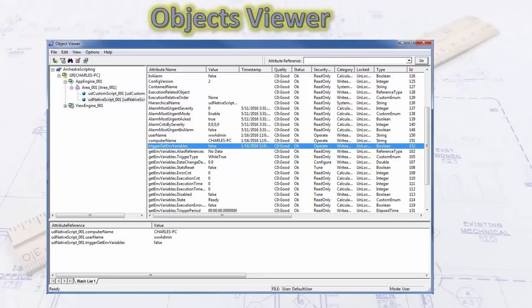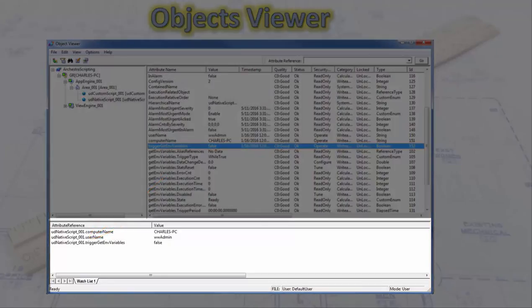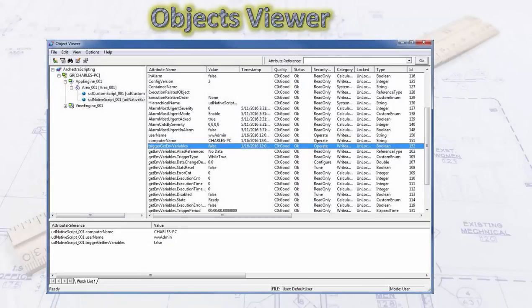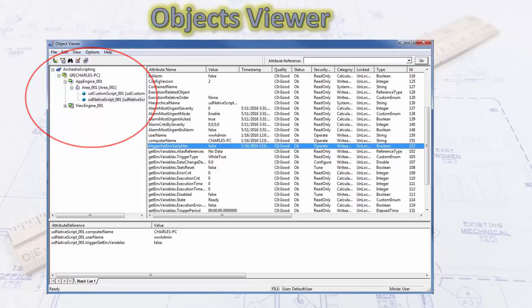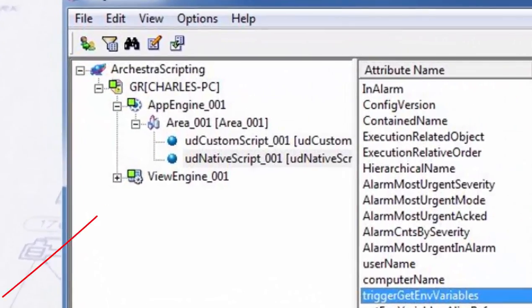The right-hand pane is a snapshot of attribute values at the time you opened the viewer. If you want to see real-time values, drag attributes from that pane into the watch window at the bottom, which updates in real time so you can see values as they change. This is a very important tool for diagnosing and troubleshooting problems in the galaxy. If there's a communications problem, an internal engine problem, or some other issue, you'll see an exclamation or error warning in the explorer pane so you can determine the health status of the object at runtime.